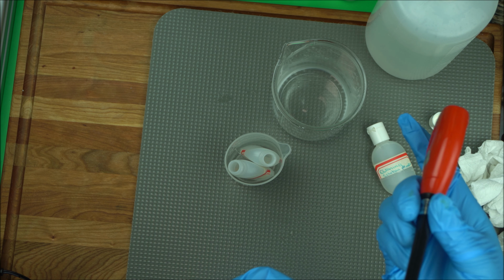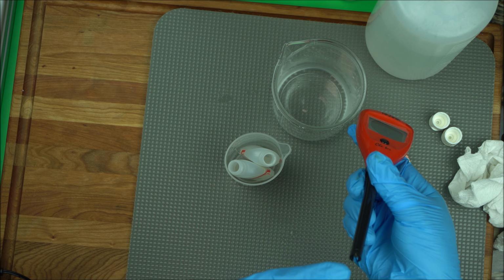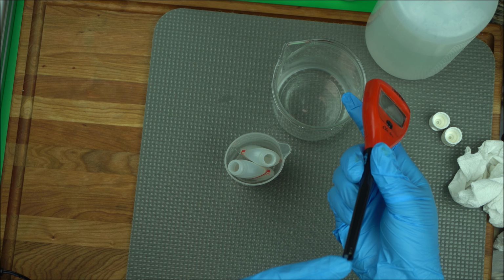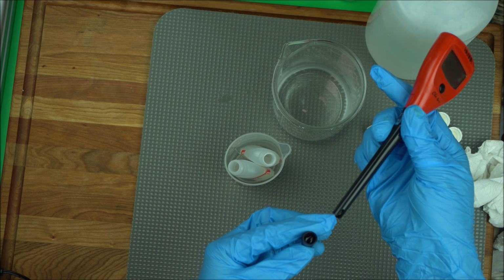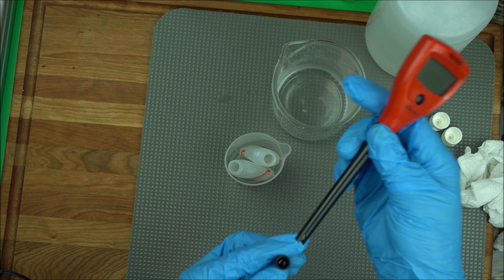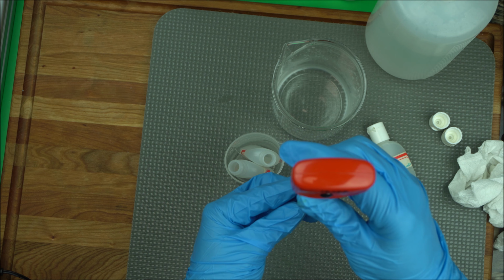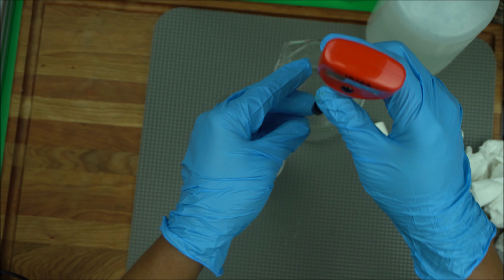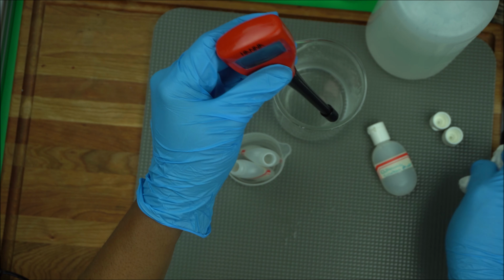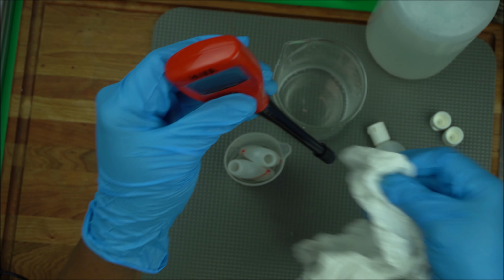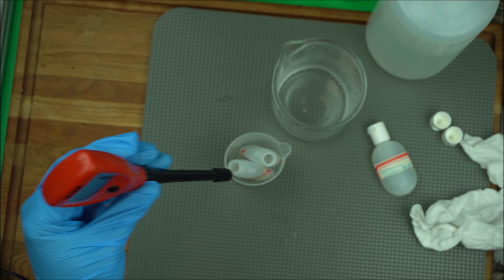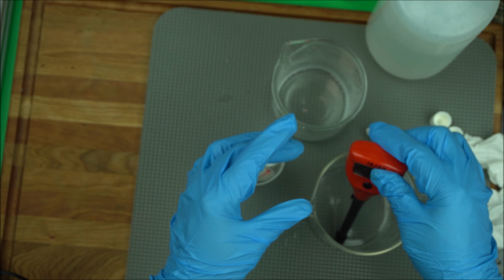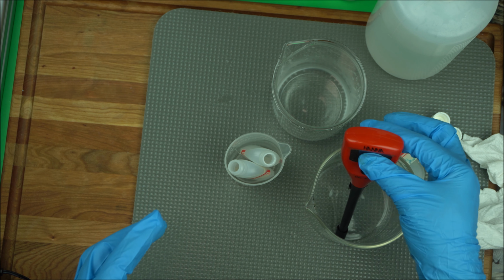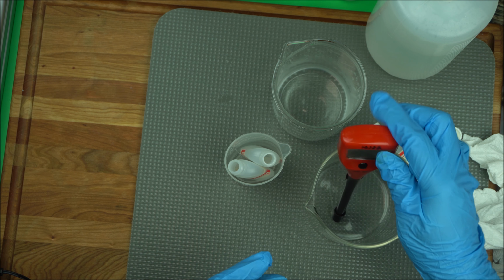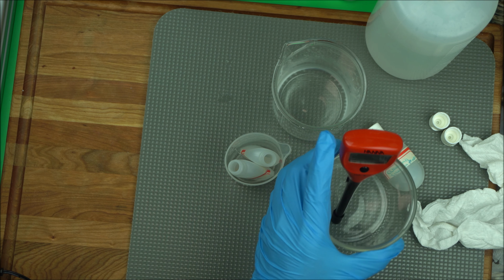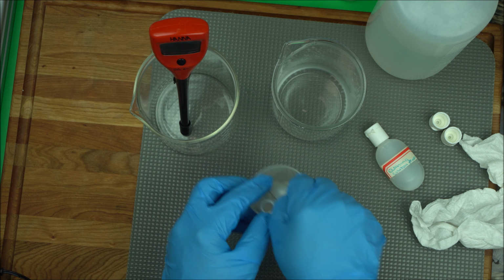That is going to help you. Remember when we were doing pH check, sometimes we dip this into that and it gets dirty. But cleaning solution is going to dissolve all the dirt for you. So put it in a cleaning solution when you're done calibrating, or when you are done using it for the day. Just make sure you put in a cleaning solution and make sure you stand it upright always. Do not do it like this. Stand it upright always, and that's how you maintain your pH meter.